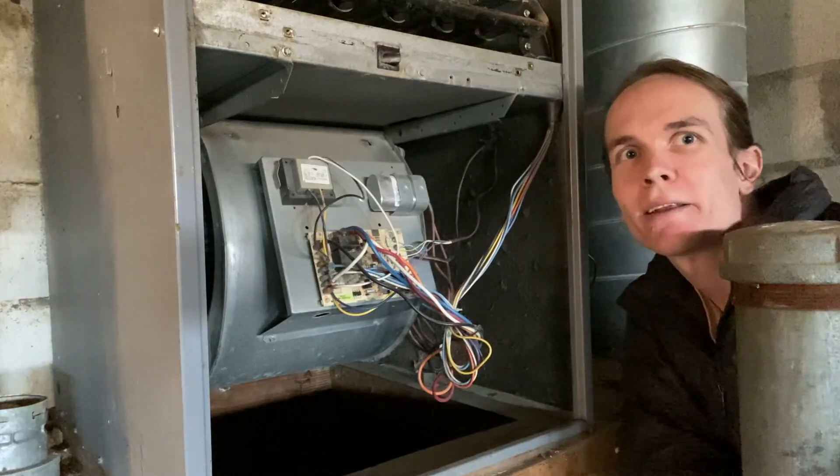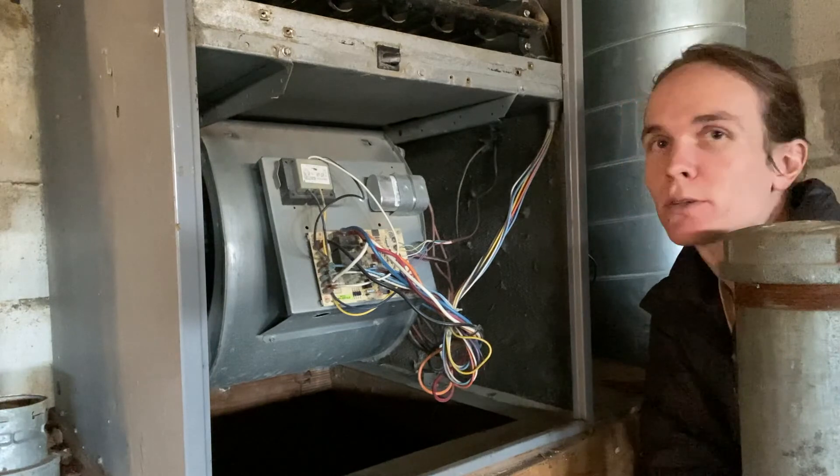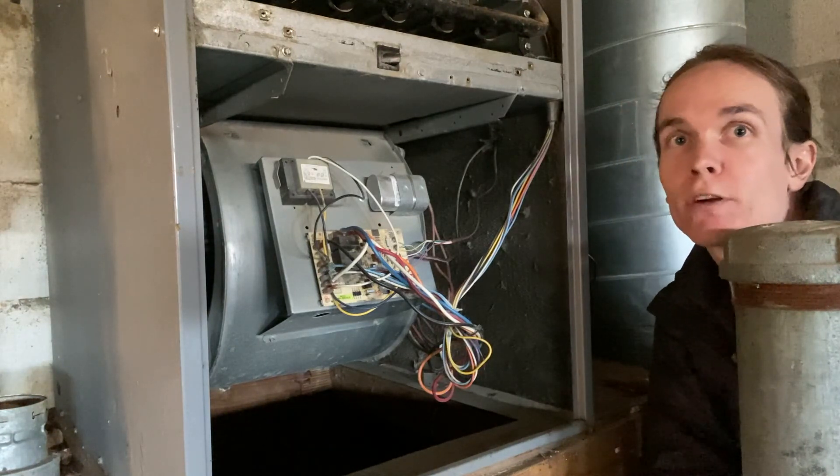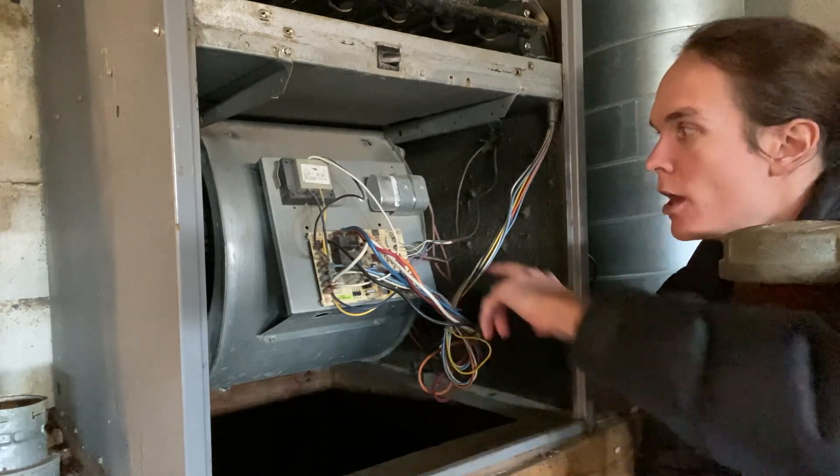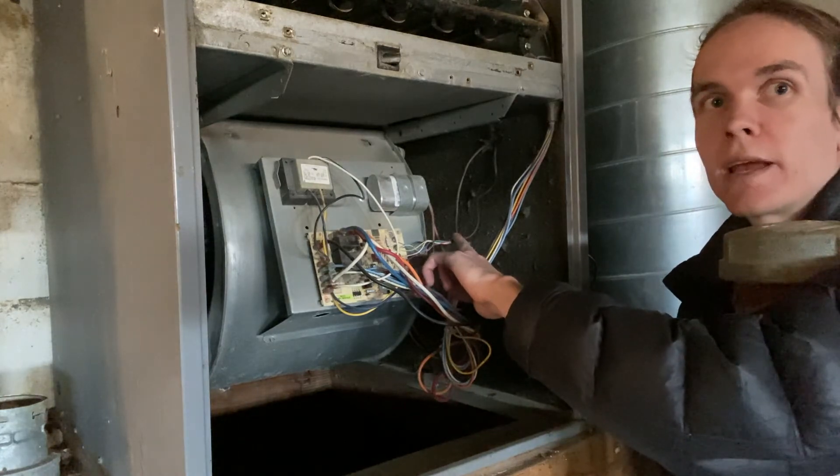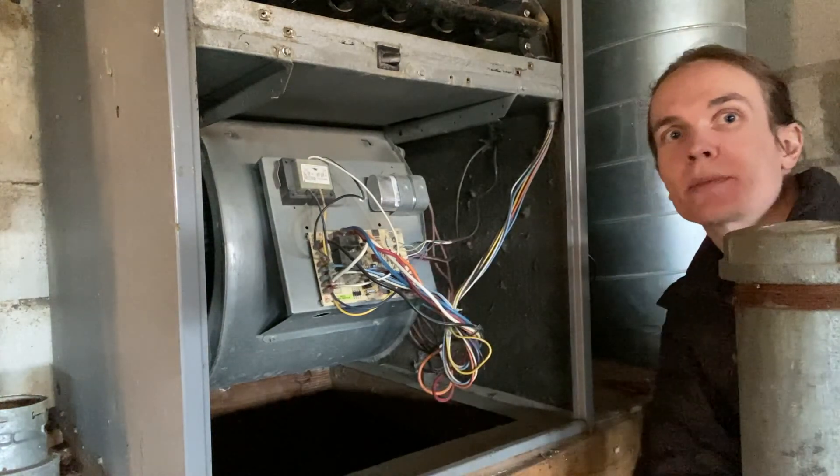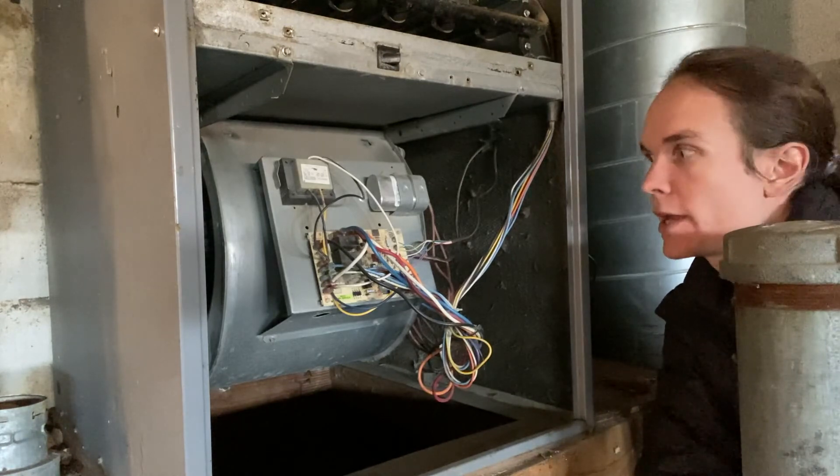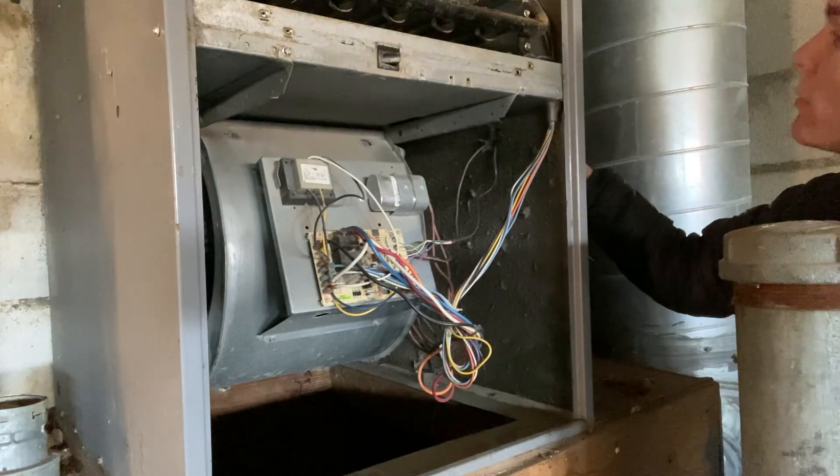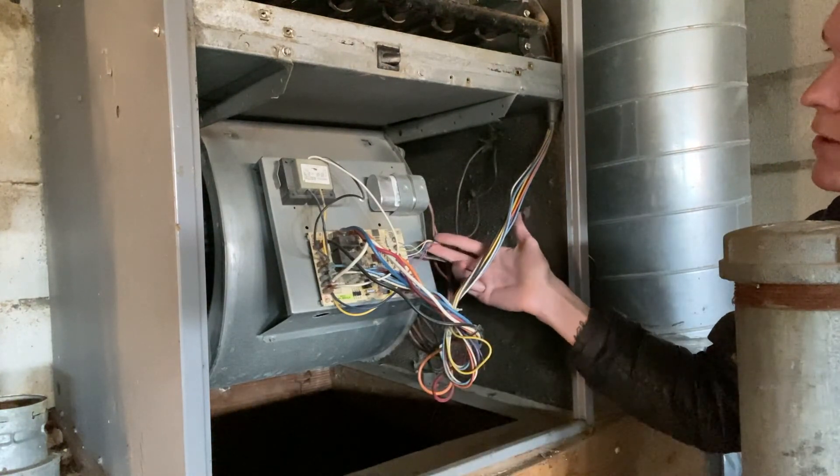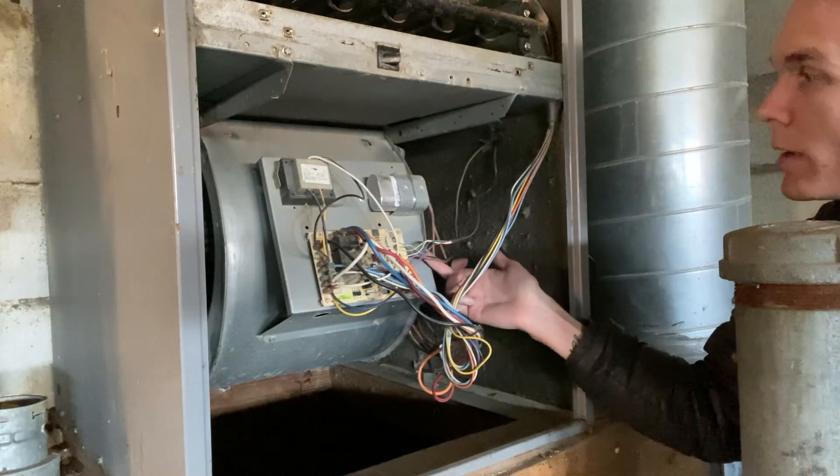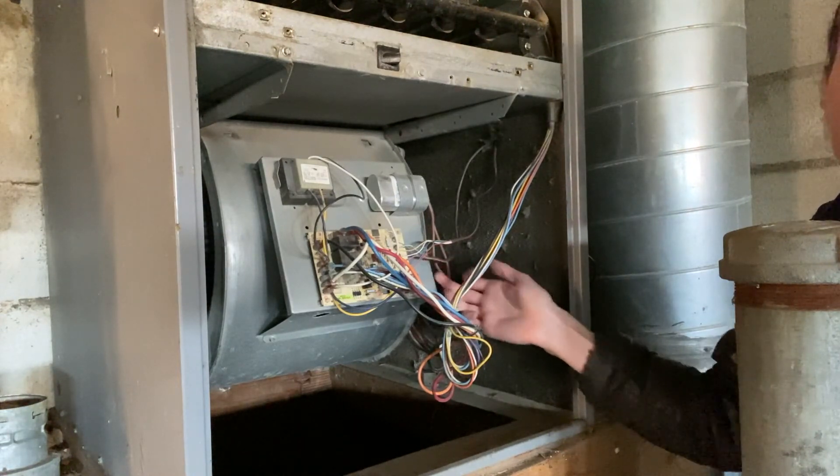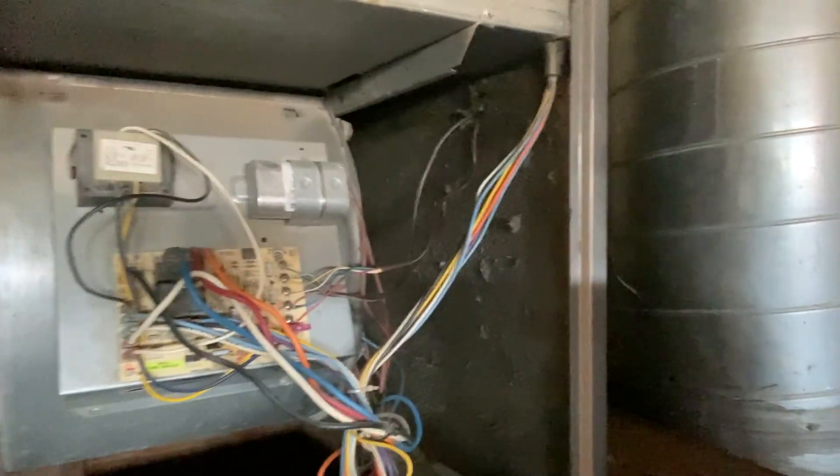I'm down in the garage. I got these giant metal pillars in the way, unfortunately. So it's a little hard to get in here. So I'm just going to show you what we're looking at first. And then I'm going to get you guys in for a close up. Here is the two thermostat wires coming in. One of them is coming from the thermostat upstairs and the other one is going outside to our AC condenser unit. We've got five wires and this one is also a five wire but the extra wires are just snipped right here.